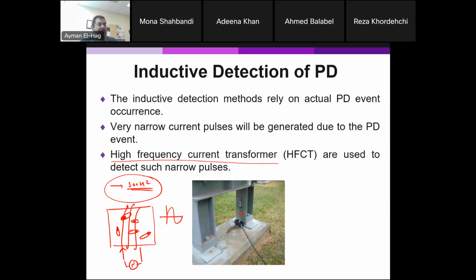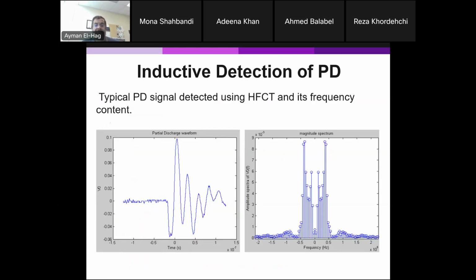This is why when you buy those current transformers, you have to make sure that you buy the high frequency current transformers. Now, as you can see here, you just put it here in the ground. Okay, so it's not intrusive, meaning that you don't need to interrupt anything. You just need access to the ground point and you have your current transformer there.